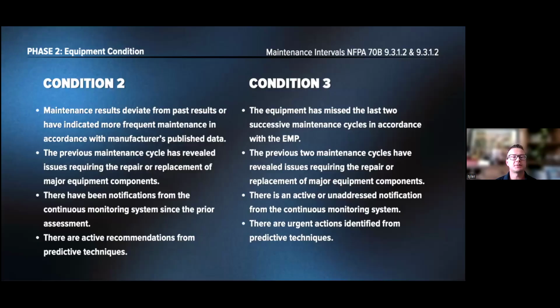Condition 2 is when maintenance results deviate from past results, indicating more frequent maintenance needed in accordance with manufacturer published data. NFPA 70B covers a high level of standardizing maintenance, but certain manufacturers know their equipment better, so they have slight variations in recommendations for what should be tested and how frequently. We provide that for you so you can have a better understanding and be more practical with everything.